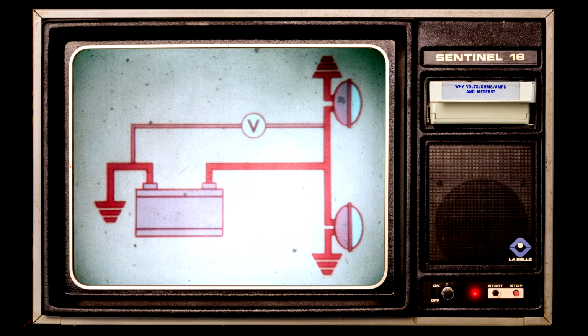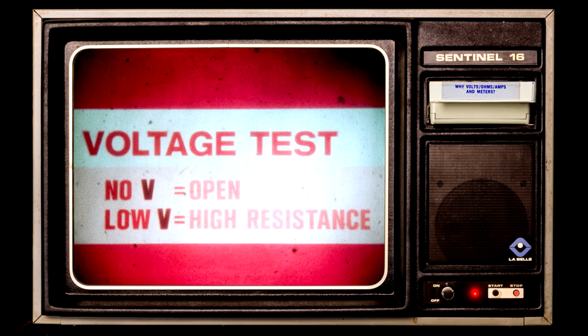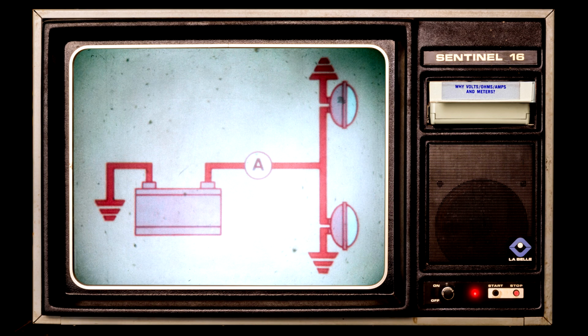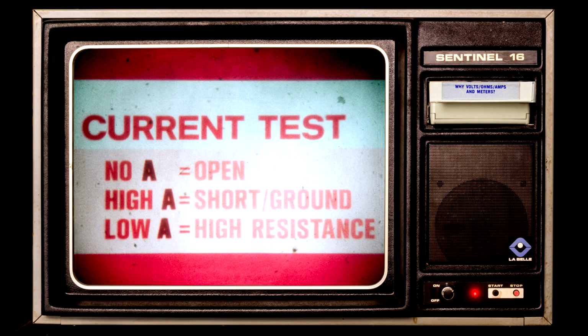Next, know how to connect the meters. This is a voltmeter hookup. Always across, in parallel with, the load or circuit. No voltage might indicate an open, and low voltage might mean you have a high resistance, corroded connection. This is how you connect an ammeter, always in series with the circuit, with the positive side toward the voltage source, negative side toward ground. Like a voltmeter, the ammeter can also tell you several things. No current, of course, would mean an open. A high, out-of-spec reading could indicate a short or unintentional ground. And if current is below specs, a high resistance fault is the cause.